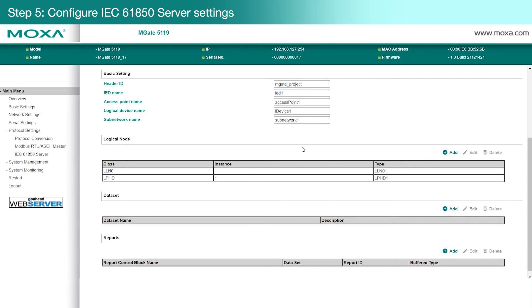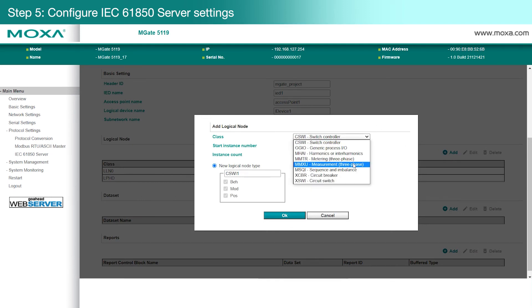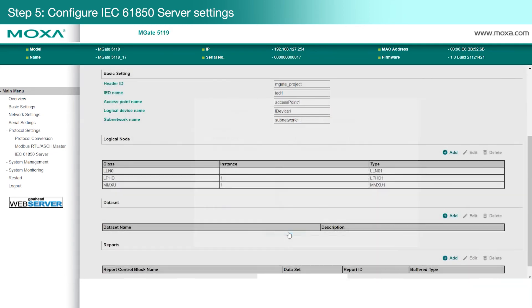The MGate will automatically load in default settings you can use, and you can change them as needed for settings such as the header ID and IED name. When you're done with the basic settings, click Add to create a logical node. We're monitoring power frequency, so we'll select MMXU for the class, and Hertz as the object. Then we'll click OK.